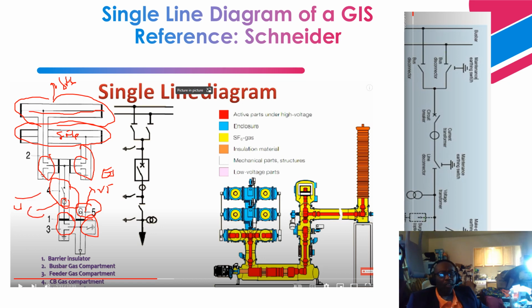Okay. So similarly on this diagram, right? Okay. Similarly, double bus arrangement, right? We have a disconnect switch, right? We have an earthing switch, and we have a circuit breaker. On this side is also another disconnect switch, earthing switch, and VT. And an earthing switch are basically the line side. We have a line disconnect and the line earthing switch. Same like we have bus disconnect switches, then we have bus earthing switches.